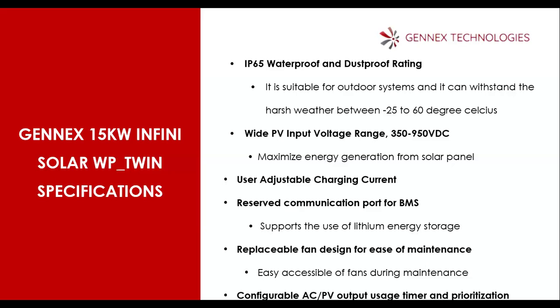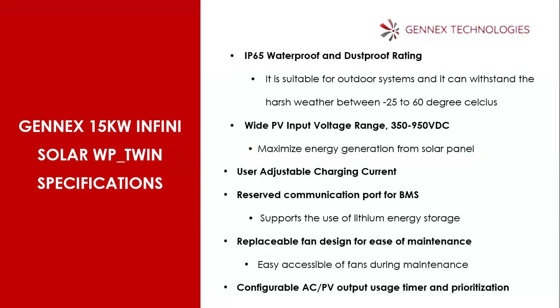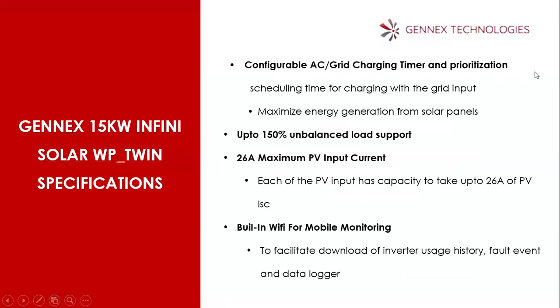Again, as a 3-phase inverter, there are some inverters where you need to balance the 3 phases in order to make the inverter work very well, but not for this one. This one can support up to 150% of the load on a single phase. Imagine maybe you have all the load on one phase. You have not been able to separate everything. The inverter can still support the load and give you up to some level of the total power rating of the inverter.